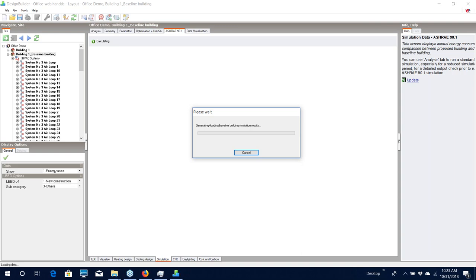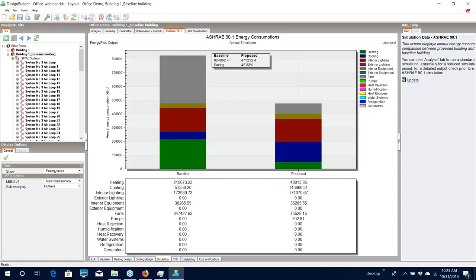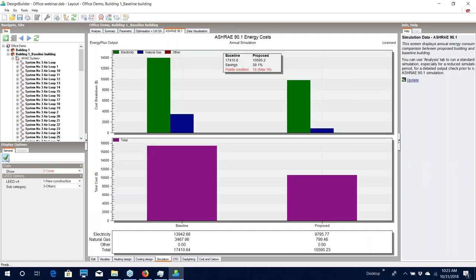While the simulations are run and the results are displayed within Design Builder, all of the EnergyPlus output files are saved to your local hard drive. It is possible to open those files and look at the results using the Design Builder Results Viewer, which displays all the output values selected from EnergyPlus, or any other output viewer you prefer. Now the baseline simulation is complete. On the screen we see the energy savings between the baseline and the proposed, which in this case is just over 42%. If we switch the display to costs, we can see that the savings is a little lower at 39%, and it gives an estimate of the LEED points that would be credited.